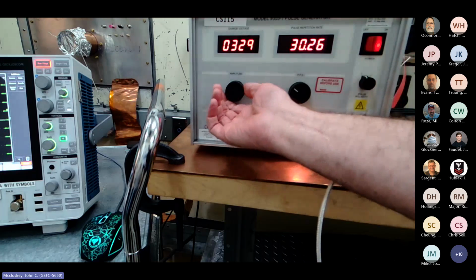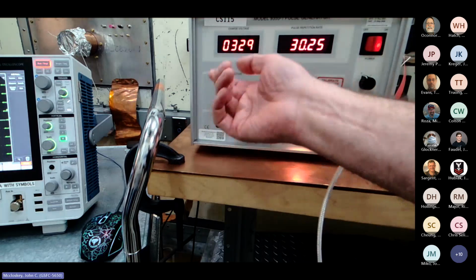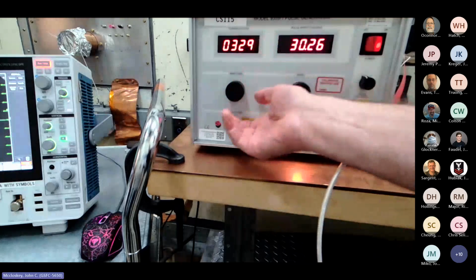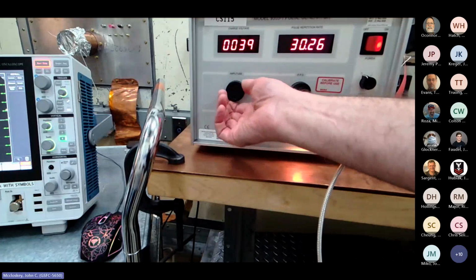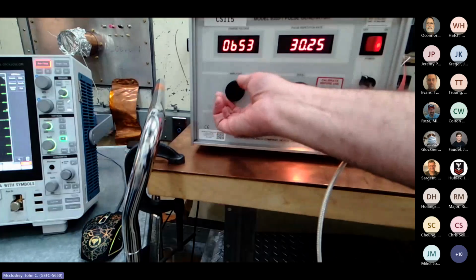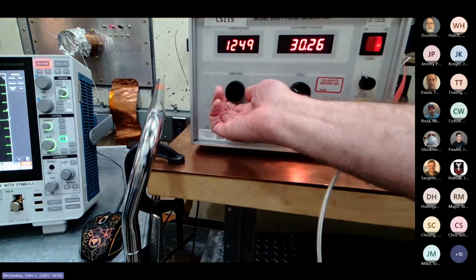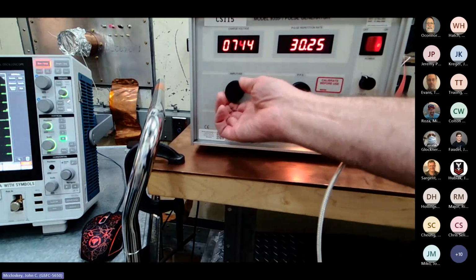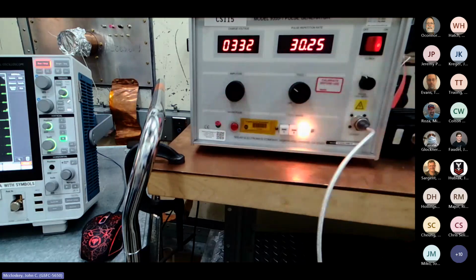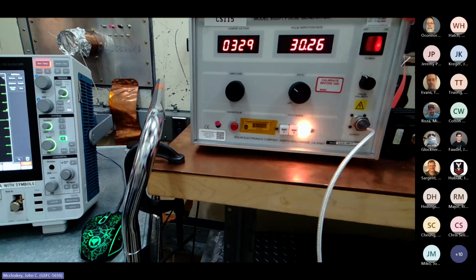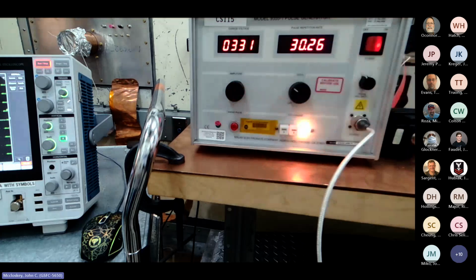Let's see how far down we are here. It says 329, I think that means millivolts, so there's 0, and full scale is about 1200. So we're at about quarter scale. But when you want to be up like half scale or higher, because then you're in the more stable part of the operation of your box, and you have a little more granularity. If you're down at like 5% scale on your potentiometer, any little adjustment you make is a pretty significant change.